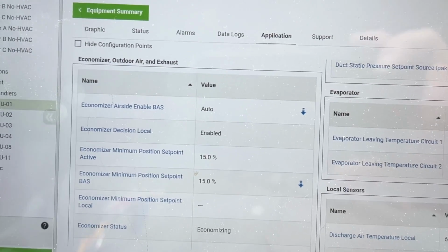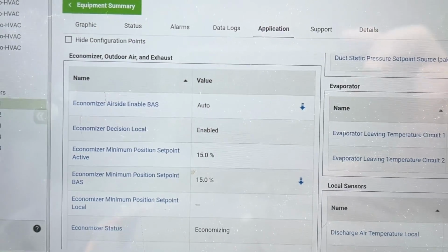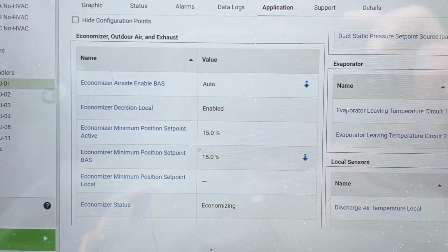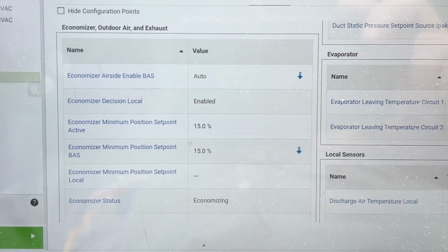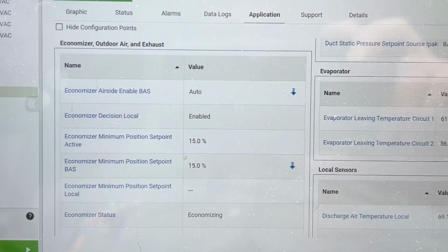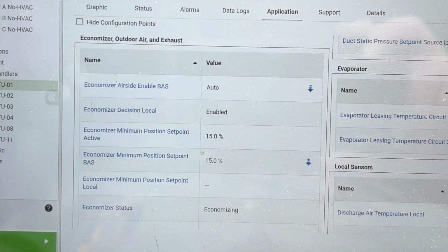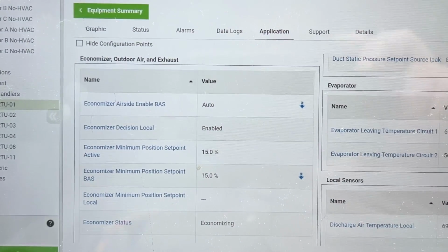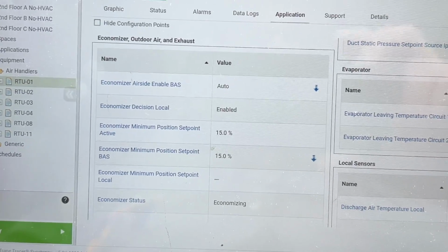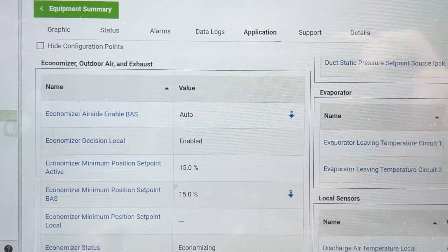So yeah, that's pretty much what I find comes with these issues with these VAV and Telepac units. Unless it's a mechanical failure, most of the time it's gonna be a programming problem. It's super annoying because we don't have access to it, so we can't go in there and change stuff. But we've been monitoring this unit for a while because that's not the only space that's having an issue. So basically, we've been finding that it's averaging out the set point of the temperature for the air handler to supply a warmer temperature than desired. So if you have a space that's, you know, 70 something degrees and you're pumping 73 degree air in there, it's just not going to cool it.